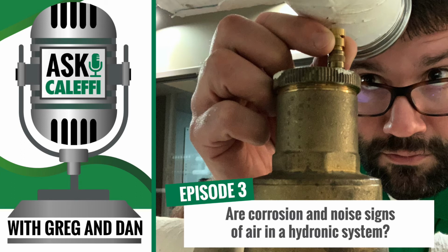They're a multi-pass device. So they will get the majority of the air out in the first pass. But being multi-pass, the next couple passes after that will continue to remove air. And actually, anytime the system's running, if there's micro bubbles in there, it's going to remove them. Right. And that's always a confusion with people too, is they get these and they don't realize they are a multi-pass, and it can also be confused and misapplied in other applications. Yeah. Plumbing in particular. We get that a lot.